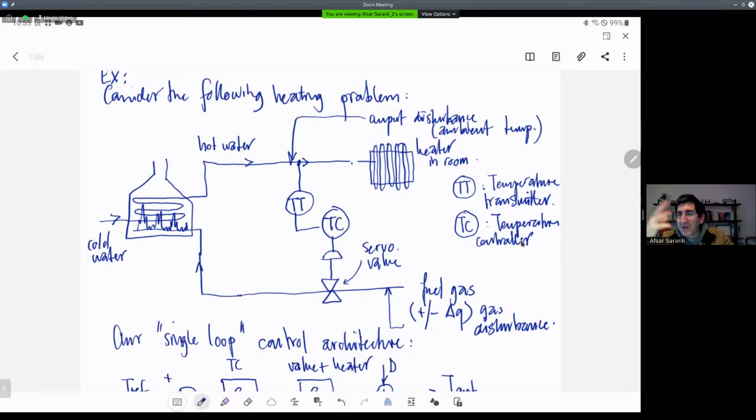So what's the alternative? What can we do? The idea is that if we can also have the ability to measure the gas flow as well as regulating it with the valve, we can actually do an earlier correction to the gas flow. If we can measure the gas flow, and we also have another controller that we will call an inner controller or a slave controller, we can regulate the gas flow in a smaller loop so that the fuel gas flow is almost constant.